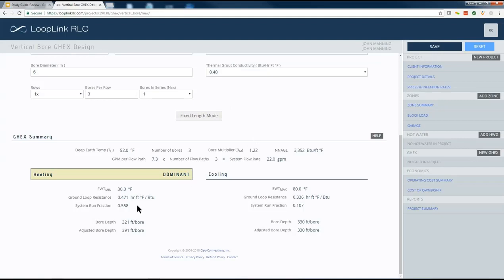But a couple things to point out here: notice the difference between the bore depth and the adjusted bore depth on the screen. If you remember from the zone summary page that I showed earlier, the ground load imbalance was what, 90 million BTUs taken out of the ground versus about 20 million BTUs put back in the ground in cooling mode. We've got a relatively imbalanced annual ground load. And that's why you're noticing the difference between the bore depth and the adjusted bore depth here.